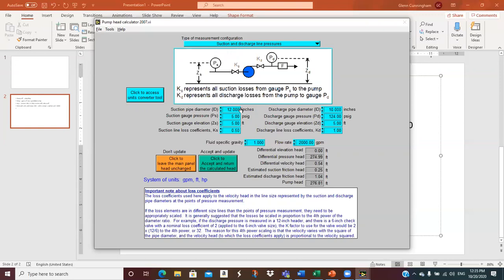But anyway, if you look at this, this is really pretty nice. On the suction side, you've got the pipe diameter. Take your tape measure and measure it. Your suction gauge pressure, in this case 5 psig, the elevation of the suction gauge, and then the suction line loss coefficients, which is probably some sort of a valve that's wide open. You usually have valves on both sides in case you have to take the pump out. It's real handy to not have to drain the system of all the fluid.